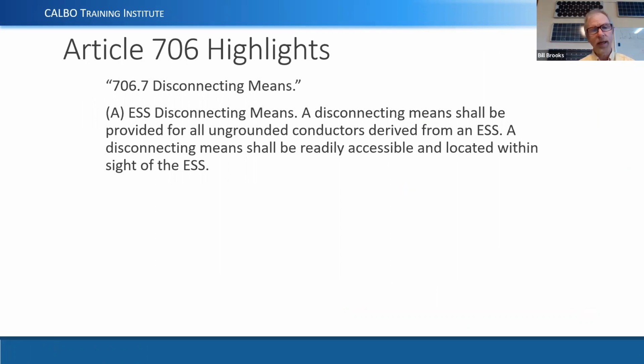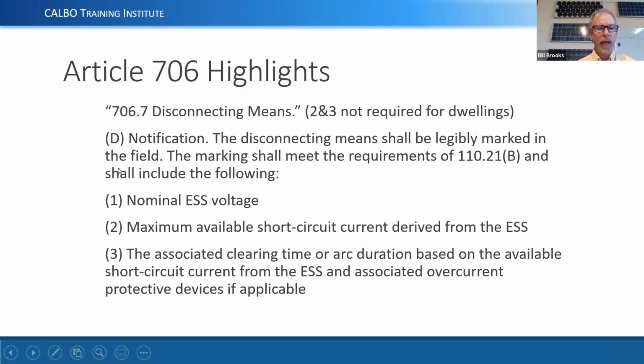706.7 covers disconnecting means. For residential systems, we just have to have the nominal ESS voltage. We're not required to have the available short circuit current and clearing time and all that other silly stuff. It's wonderful stuff, I should say. As an engineer, it's fun, exciting information, but it's not required for residential.